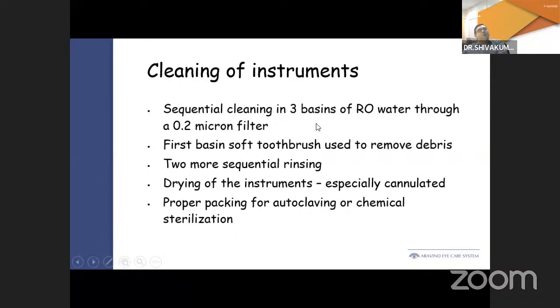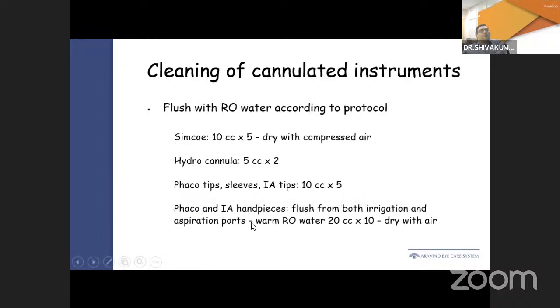And then a sequential cleaning is done in 3 basins of RO water. And this water is collected through a 0.2 micron filter. In the first basin, a soft toothbrush is used to meticulously remove all the debris, and then 2 more sequential rinsings are done. Equally important is the drying of the instruments, especially the cannulated ones, because the damp or water-containing cannulae do not get autoclaved or sterilized properly. Also important is the proper packing of these instruments for autoclaving or for chemical sterilization, because if they are too closely or tightly packed, this may not happen properly.